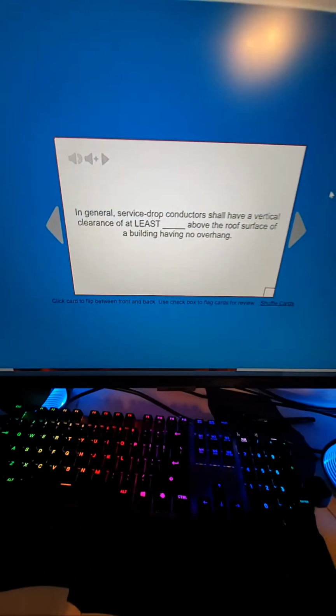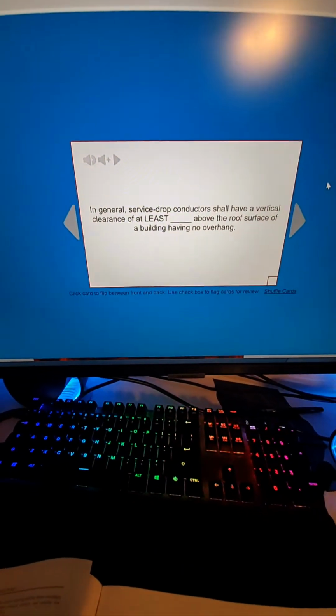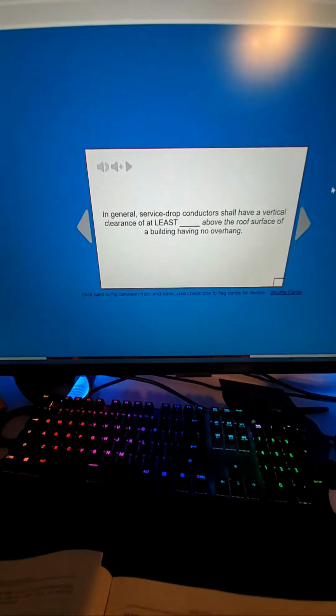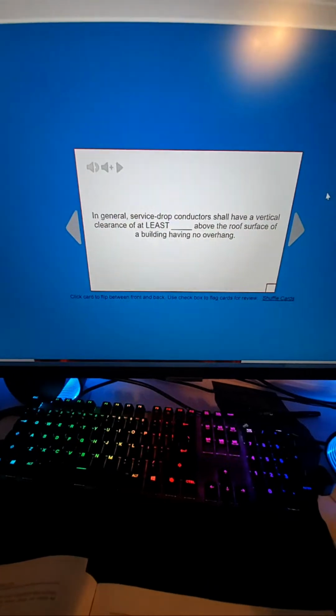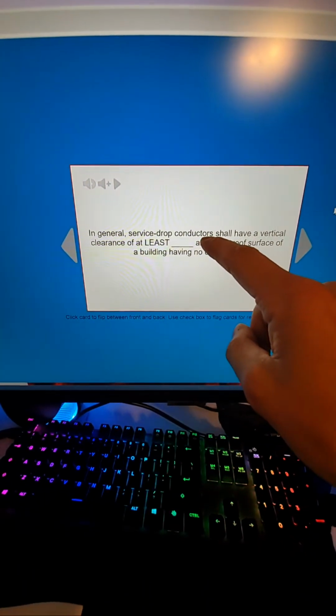In general, service drop conductors have a vertical clearance of at least blank above the roof surface of a building having no overhang. So right there, the keyword is service drop conductors. We already kind of know where this is going to be. Like I said before, my book is falling apart, and it's a 23. I go in this thing so much. But if I was to make a guess, we would probably look at the beginning of this book, in the 200s, where it talks about services, because it's a service drop, which should be 230.